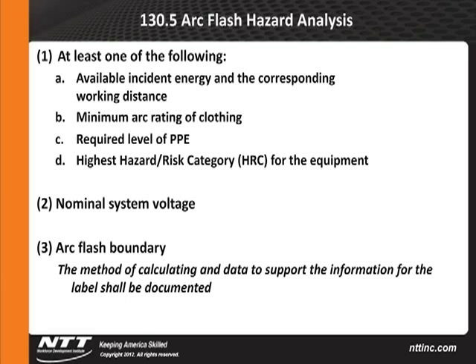I often get asked, I've got a label out there. It says 40 cals. Do I have to do that when I'm simply doing switching? And the answer is yes. You protect yourself from the highest potential hazard. Item number 2, the nominal system voltage of that equipment, 120, 208, 277, 480, 4160, and so forth. And item number 3, the arc flash boundary. Now, the method of calculating the data to support the information for the label shall be documented. In other words, are we using the IEEE 1584 calculator? Are we using some other software, SKM, and so forth? It's got to be recorded and documented someplace.